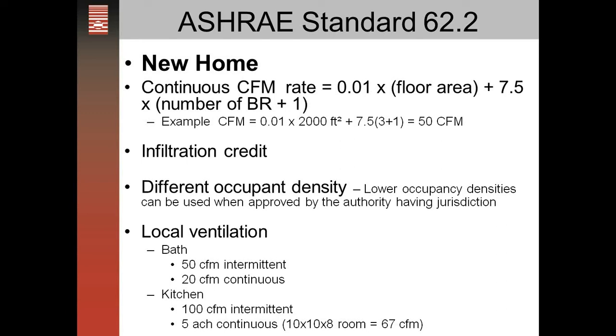For a kitchen fan, the requirement is 100 CFM intermittent or five air changes per hour continuous. For example, a 10 by 10 by 8 foot kitchen would be 67 CFM continuous.